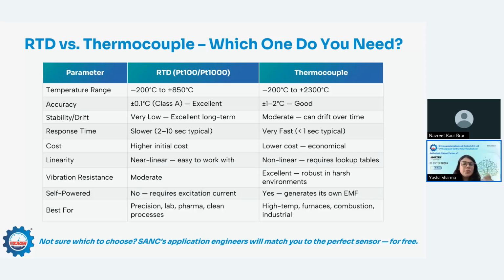I've told you the basic differences in how to select an RTD or thermocouple. But if you are still confused about what you should go with in your application, RTD or thermocouple, and which type of thermocouple or which type of RTD, should I go with PT100, PT1000, 2 wire, 3 wire, 4 wire, then I am there. We are here to help you, and we will understand your application and suggest the best solution for it.